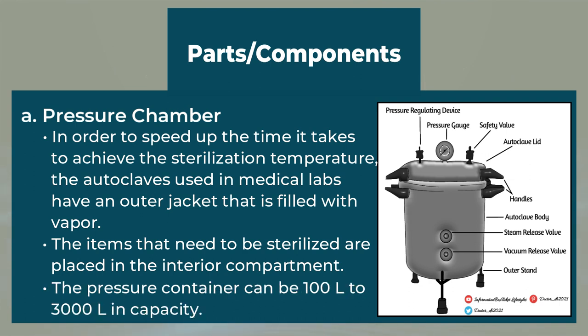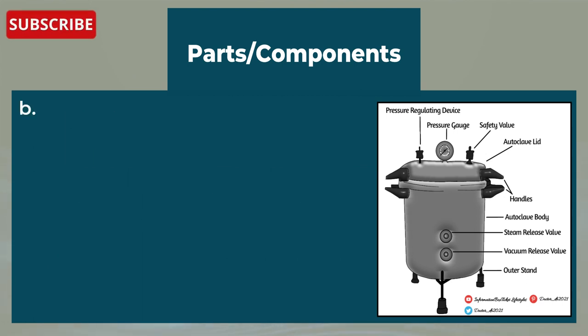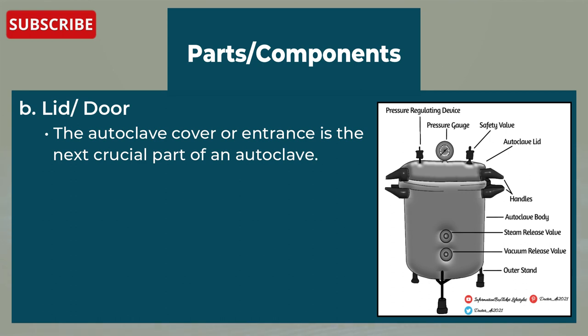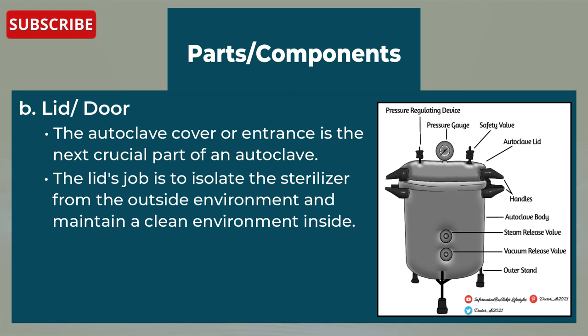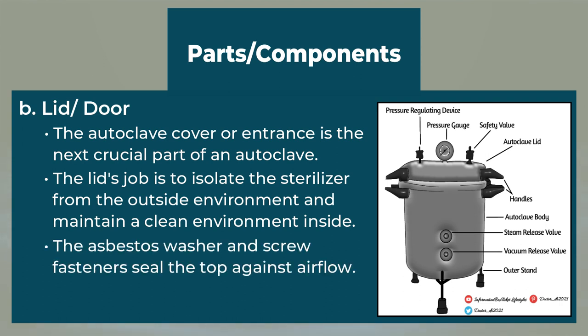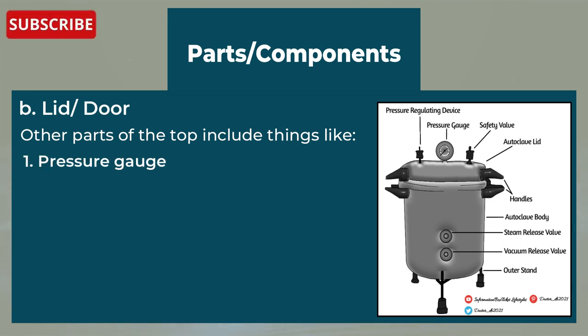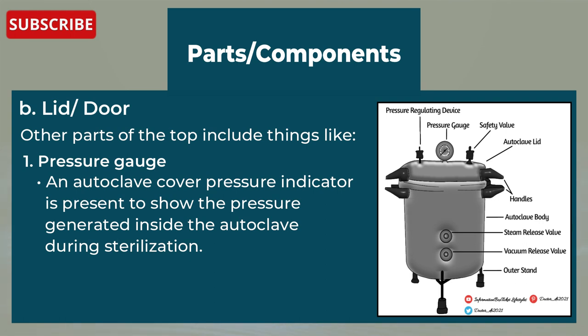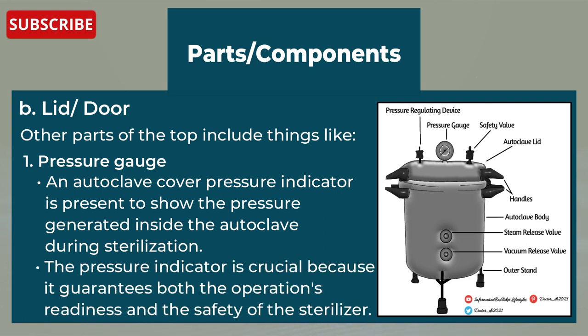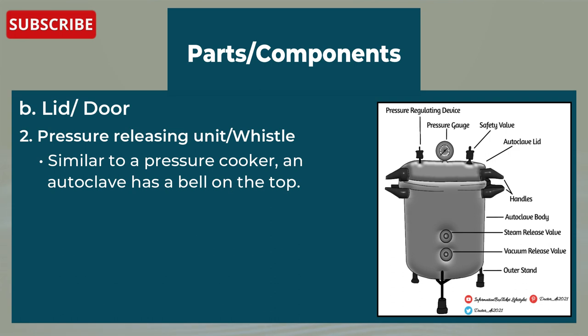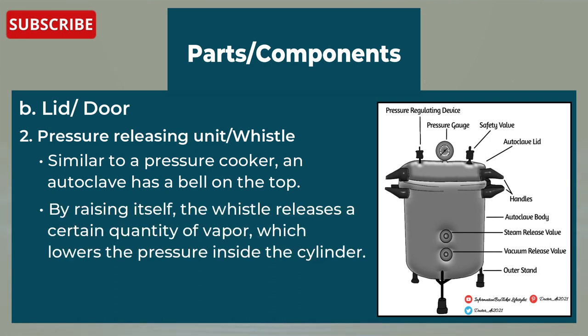The pressure container can be 100 liters to 3000 liters in capacity. Then comes the lid or door. The autoclave cover is the next crucial part — its job is to isolate the sterilizer from the outside environment and maintain a clean environment inside. The asbestos washer and screw fasteners seal the top against airflow. Other parts of the top include: a pressure gauge, which is present to show the pressure generated inside the autoclave during sterilization, and is crucial for operational readiness and safety. Also, a pressure releasing unit or whistle — similar to a pressure cooker, an autoclave has a whistle on top that releases a certain quantity of vapor, lowering the pressure inside the cylinder.